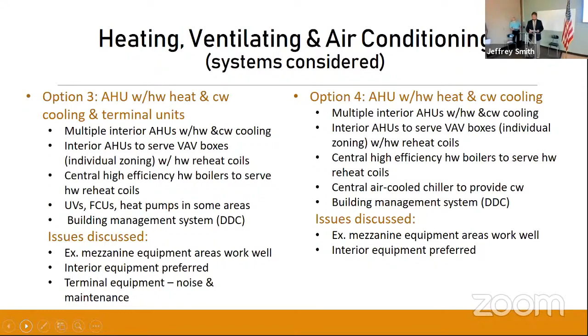Any issues that we discussed? Again, the existing mezzanine equipment areas work well. We would look at continuing that into the addition and reusing the mezzanine levels that you currently have. Again, interior equipment was preferred. So the system that we were proposing or considering for this facility is option number 4 with the interior air handling units. It's a very efficient system. We can employ demand control ventilation with the system and adjust the outside air. We have the equipment within the building, which makes it easier to maintain and increases the life of the equipment. We're able to build some redundancy without oversizing the equipment in the boiler plant and the chiller plant.